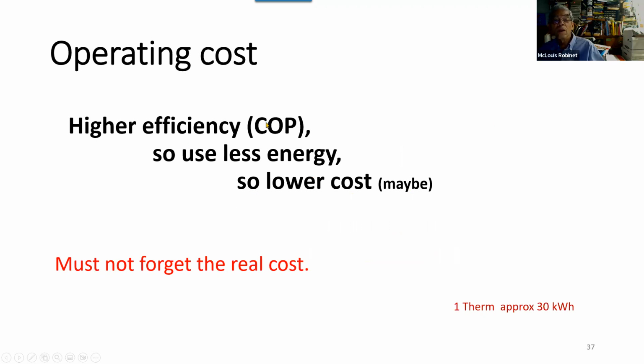So what about costs? Because a heat pump has a coefficient of performance greater than 1, anywhere from 2 to as much as 5, we use less energy than any gas-fired system. But people rightly point out that right now in Illinois, the cost of electricity is higher than that of gas. So for example, if the cost of electricity was twice that of gas, and we have a coefficient of performance of 2, then we're using half the amount of energy.